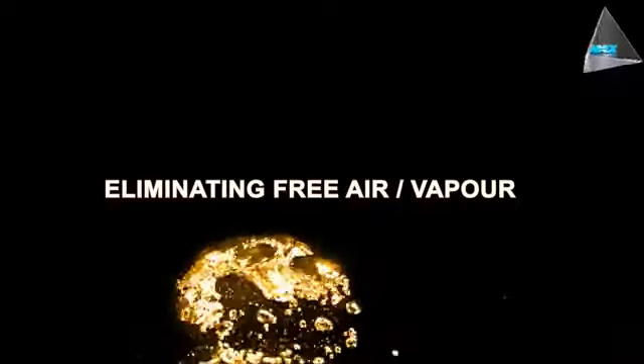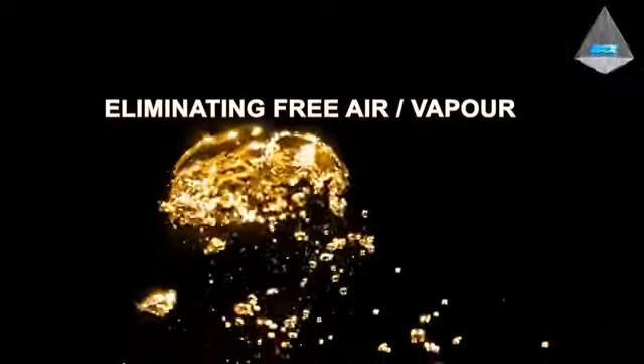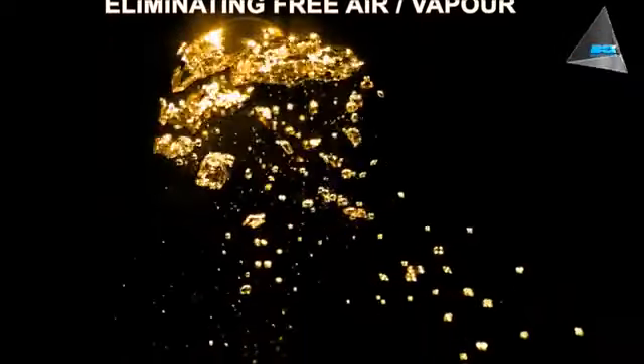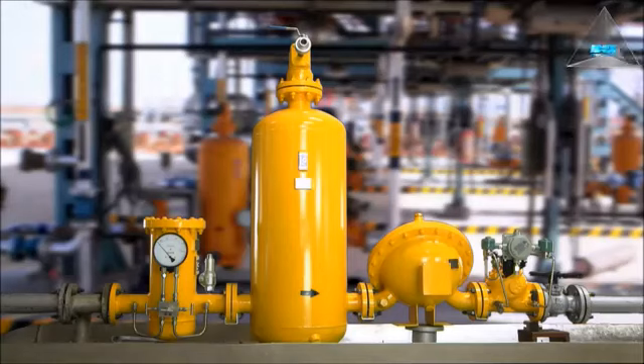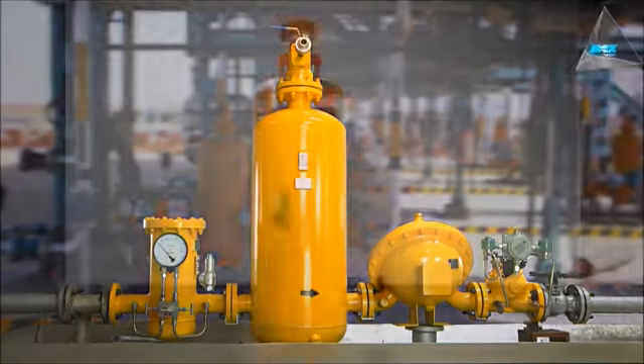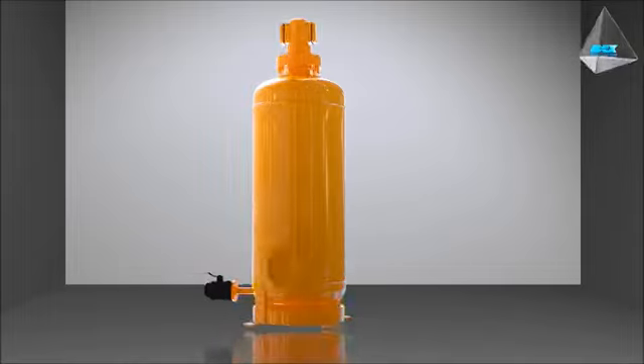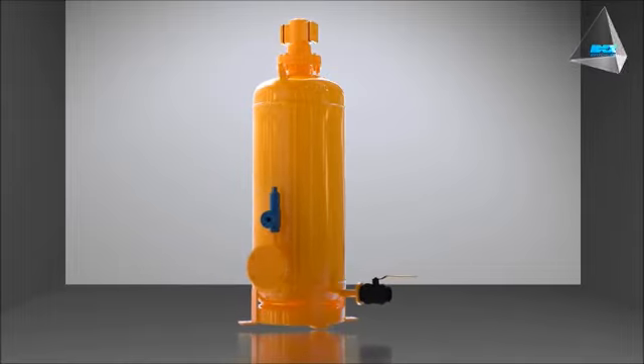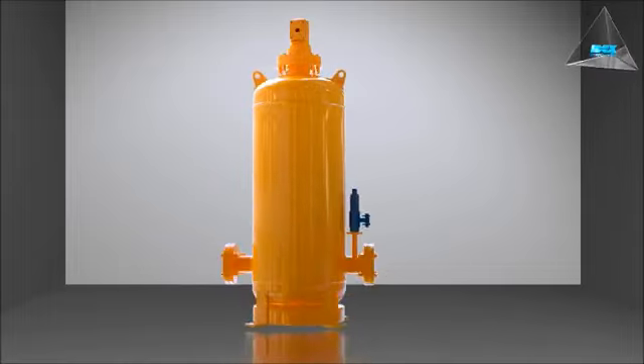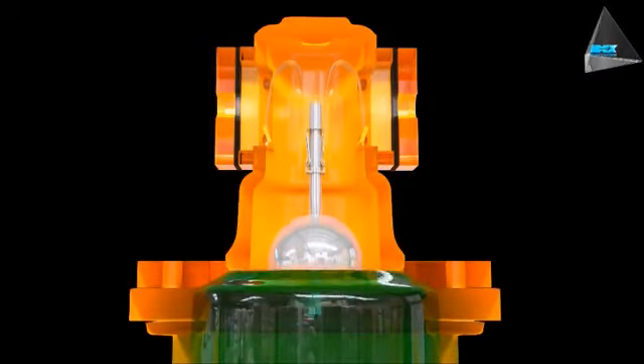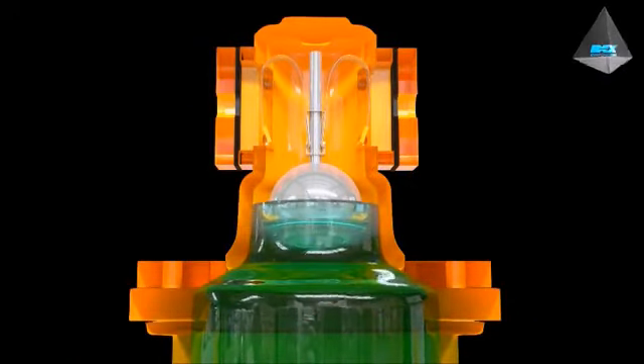Liquid Controls air eliminator. Eliminating the free air or vapor. The product is pumped through the system and enters the air eliminator. If free air or vapor is present, the pumping system moves the free air into the air eliminator. Once in the air eliminator, the air rises and vents from the center vent ports.